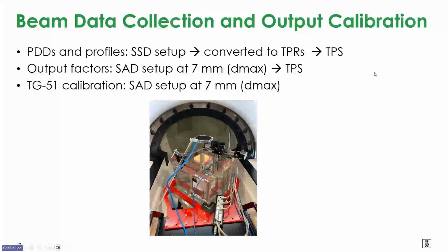For beam data, we have to use a 3D water tank, and you have to remove the end of the couch and then install all this. PDD and profile were done in SSD setup, and then we had to convert to TPR and enter into the TPS. Output factor was measured in SAD setup at dmax, and then entered in the TPS. And then you do TG51 calibration. We used the SSD setup and multiplied by the inverse square correction. So calibration is done in SAD setup, to tweak the output.